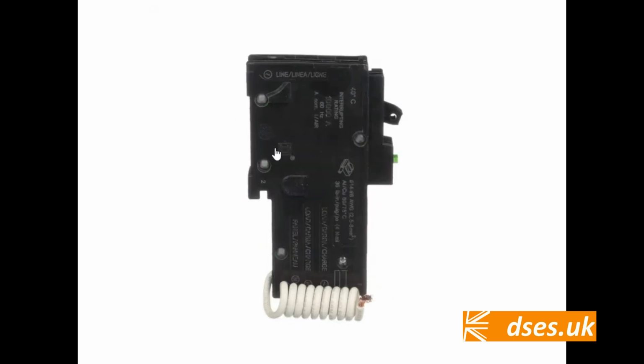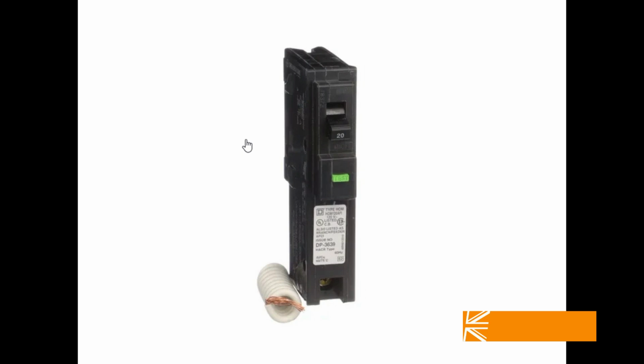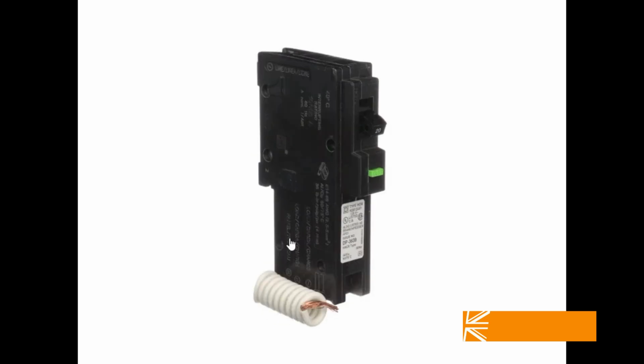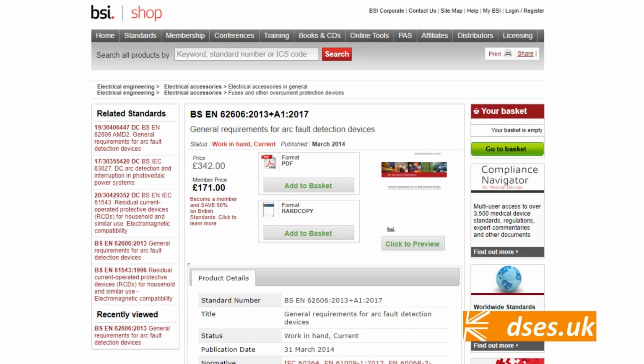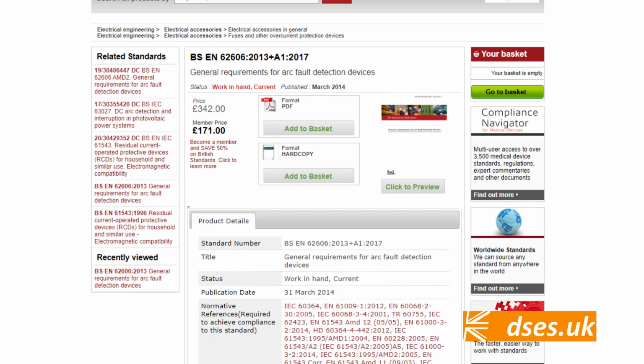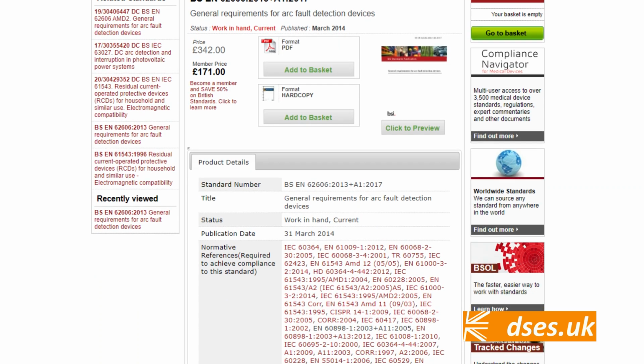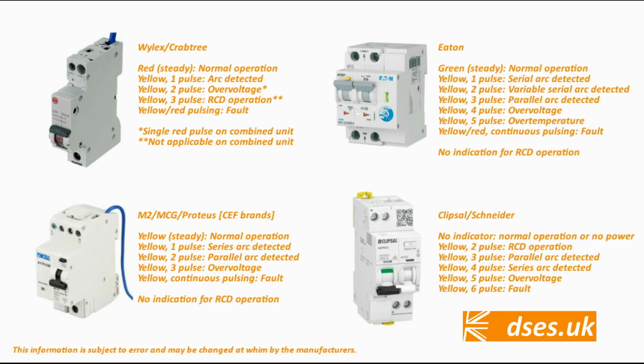I don't care that not all arc fault detectors are made equal. If they're all doing the same job, we as a species could at least have picked a single universal designation for them in English. And while I'm moaning about standardization, it's also a pain in the arse that BS EN 62606, yeah, get used to that number, didn't take the opportunity to specify how the status indicators or flags should work.